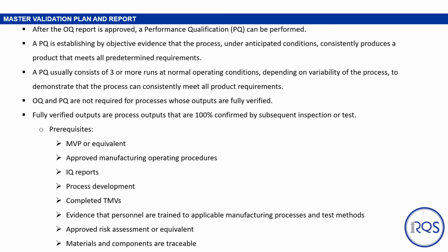OQ and PQ are not required for processes whose outputs are fully verified. And so again, fully verified outputs are process outputs that are 100% confirmed by subsequent inspection or test. Prerequisites include the MVP or equivalent, approved manufacturing operating procedures, IQ reports, process development, completed test method validations, evidence that personnel have been trained to applicable manufacturing processes and test methods, approved risk assessments or equivalent, and materials and components that are traceable.